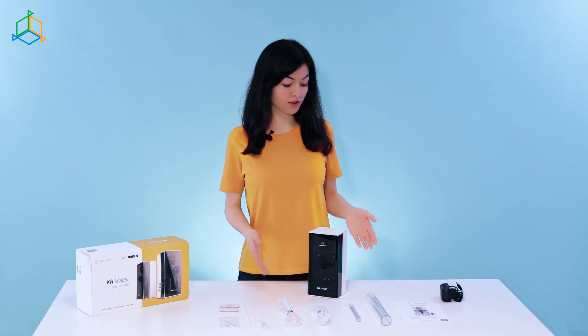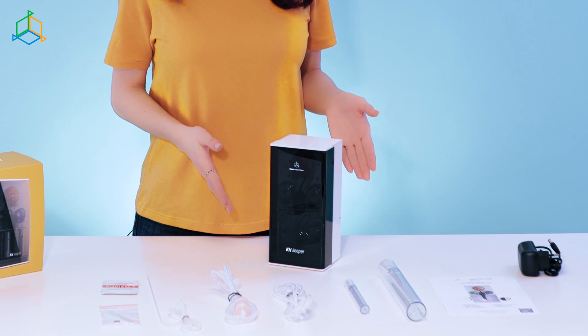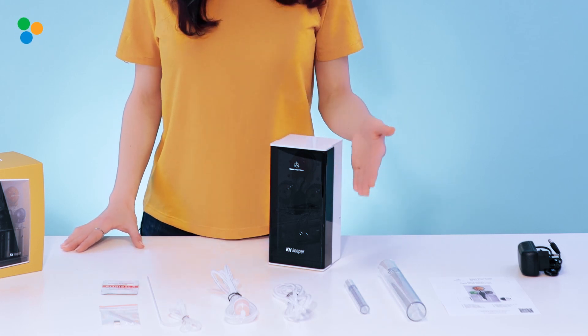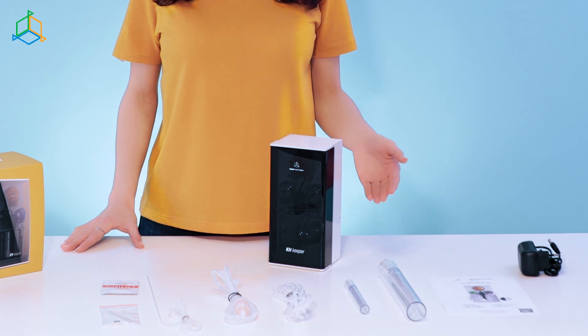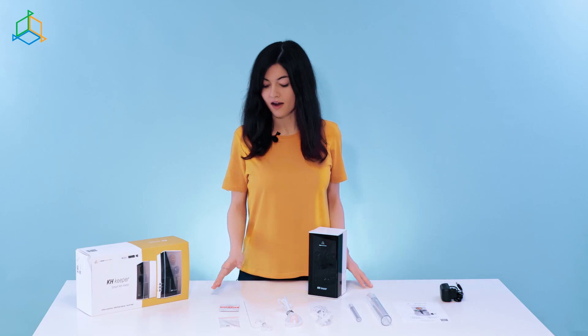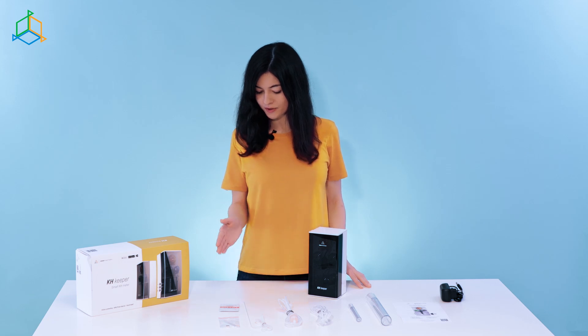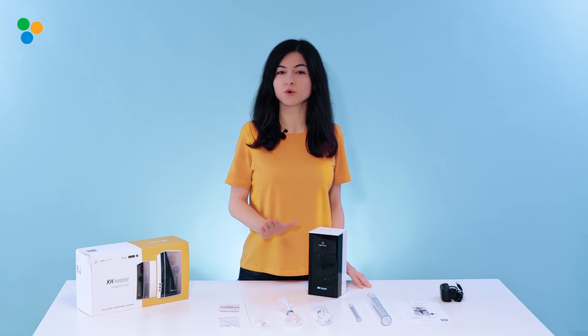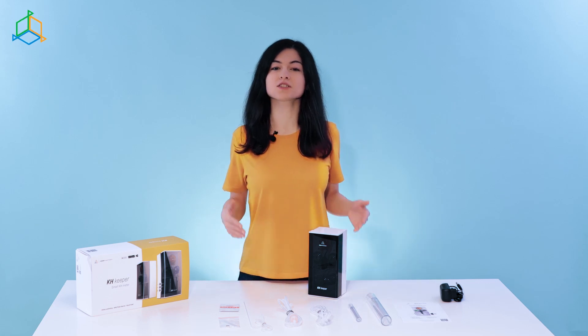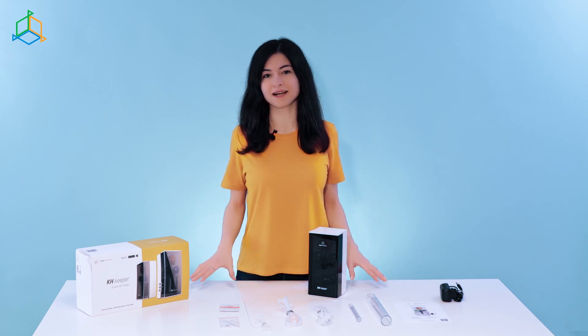The package contains the device which measures the KH level, two measuring glasses for calibration of the pumps — 10 mL and 100 mL — three different silicone tubes, a power supply, a resetting magnet, two sachets with calibration powder for probes PH4 and PH7, and a QR code which takes you to the instruction manual, which you can read in multiple languages.